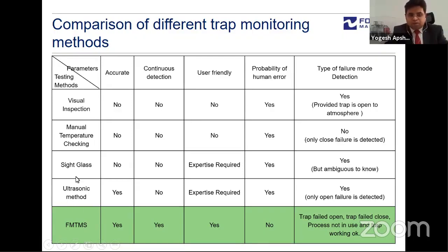If you see, we have mapped these against different parameters, like whether it is accurate, whether it has continuous online detection, whether it is user friendly or needs skilled labor, what is the probability of human error, and the type of failure mode detection, whether it is open or closed, and if closed, whether it is fail closed or fail open. The online trap monitoring system is accurate, has continuous detection, is user friendly, doesn't need skilled labor, has no probability of human error, and the failure modes it detects are open, trap failed closed, and not in operation. All these parameters we can check.